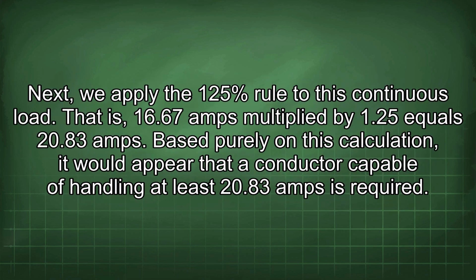Next, we apply the 125% rule to this continuous load. That is, 16.67 amps multiplied by 1.25 equals 20.83 amps. Based purely on this calculation, it would appear that a conductor capable of handling at least 20.83 amps is required.